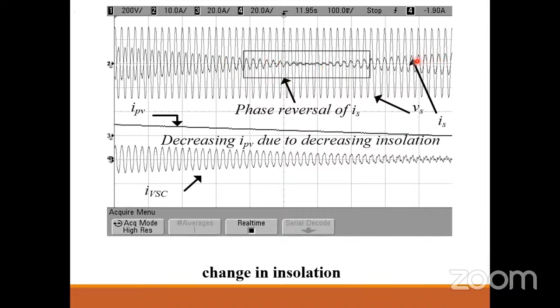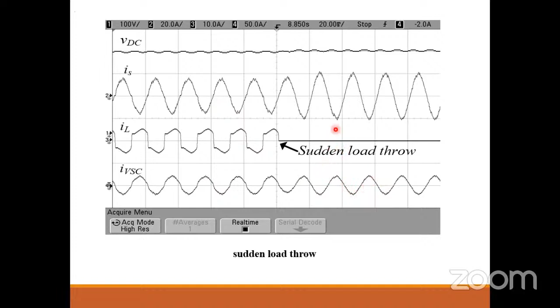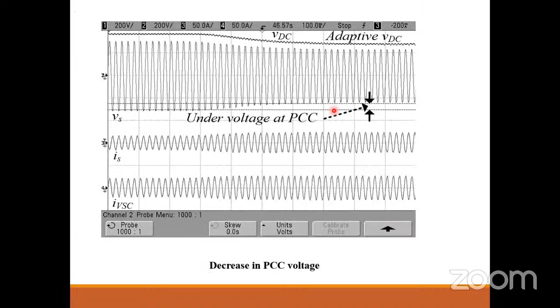Similarly, for sudden load unbalance, suppose the load goes to 0. Then the total current will go inside the grid. You can see these signals: when the load current is 0, only the PCC current is sinusoidal, and it is pure sinusoidal. But here it is not pure sinusoidal, because it's the addition of this and this. This time it's pure sinusoidal because only the active component is going inside the grid.